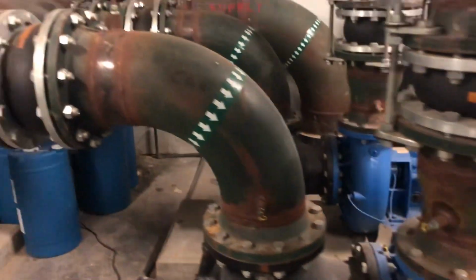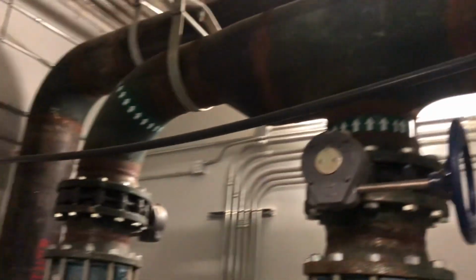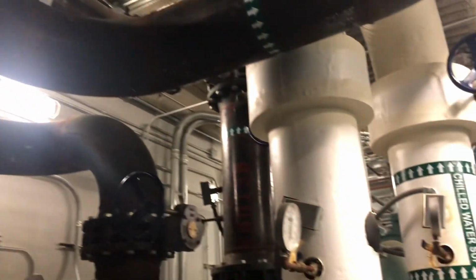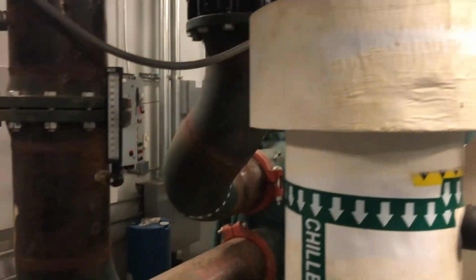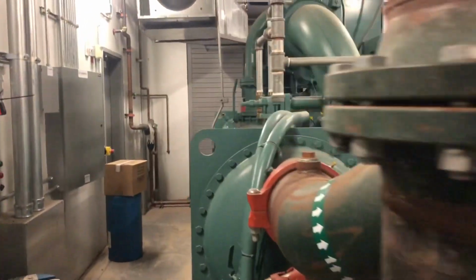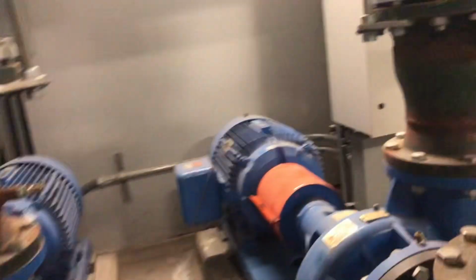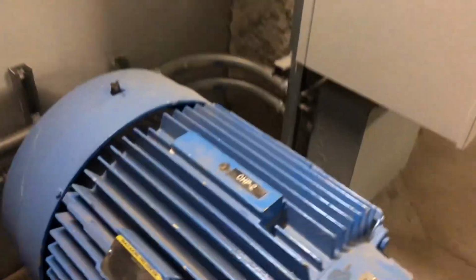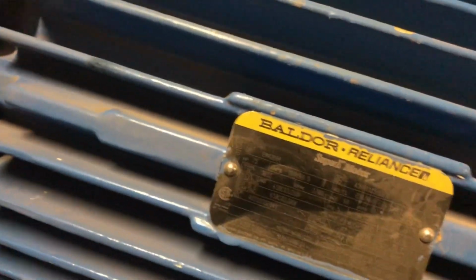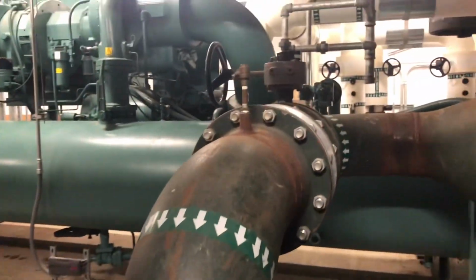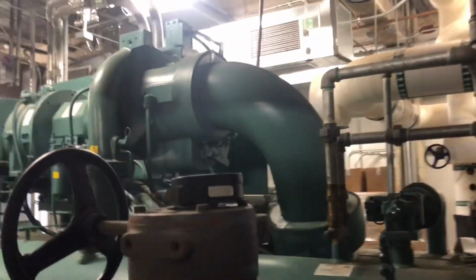These are the drives. Two of them are for the two condensing pumps that I have on this one, and the other two are gonna be for the chill water pumps. Right now we're looking at the piping. As you can see, one side is the chill water, and the other side is the condensing water. See, condensing on the left, chill water on the right. And these are all our pipings on this, and I'm gonna show you the horsepower on this motor, which I think is 75 horsepower when I looked at it. And you can kind of identify by the size what kind of horsepower motor you will have.